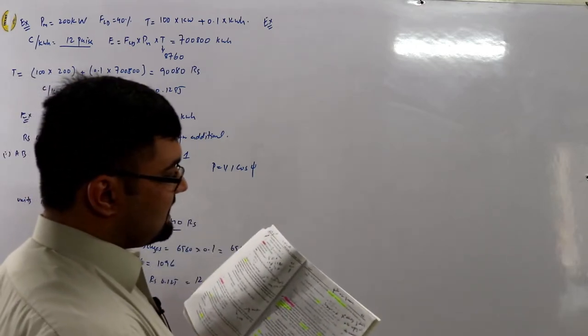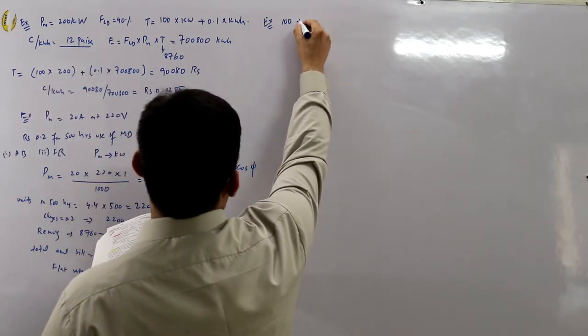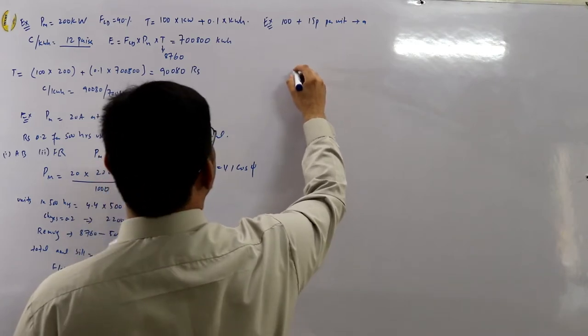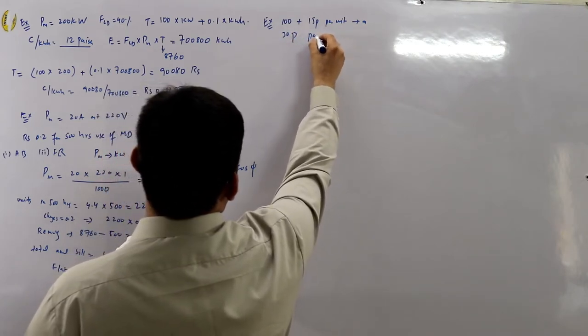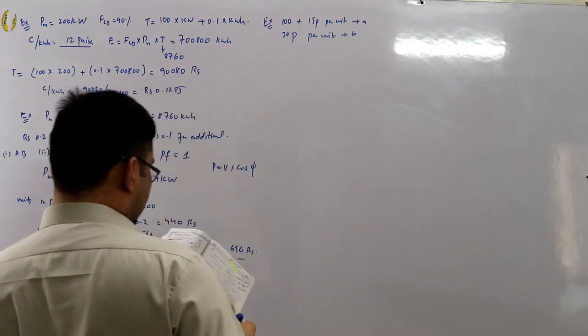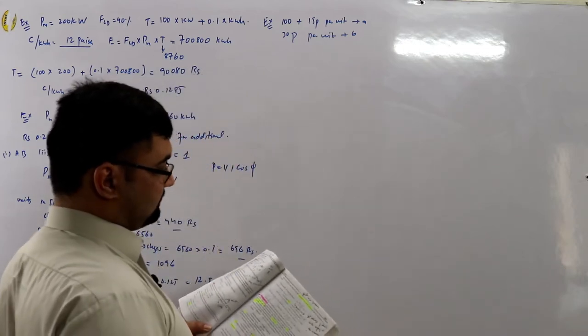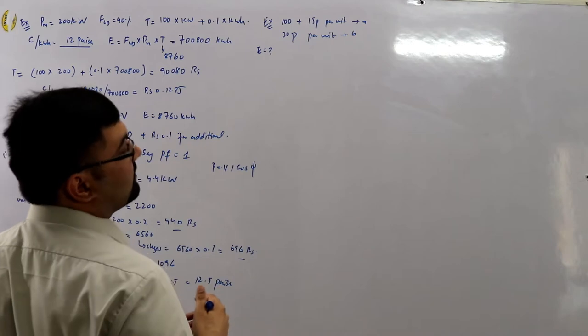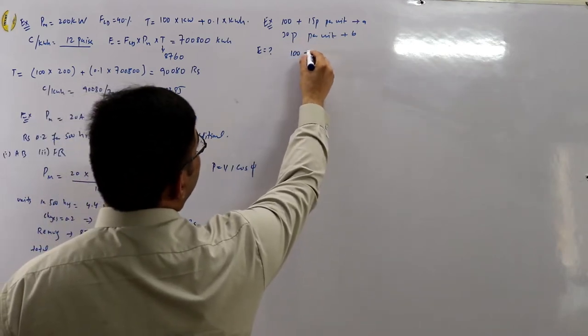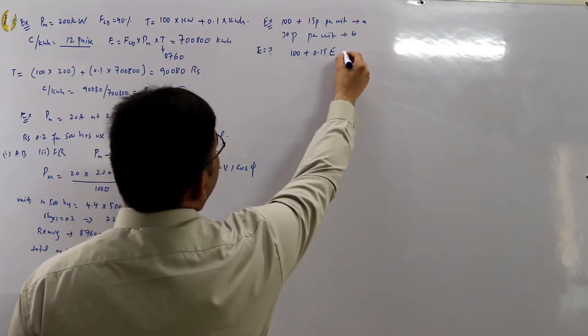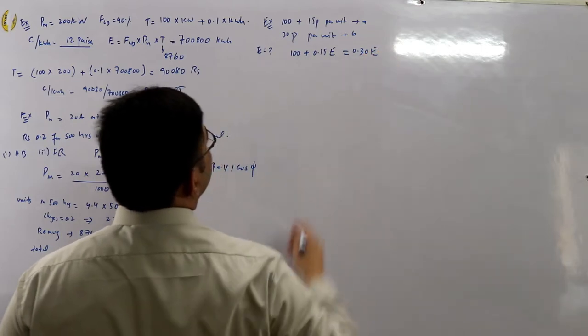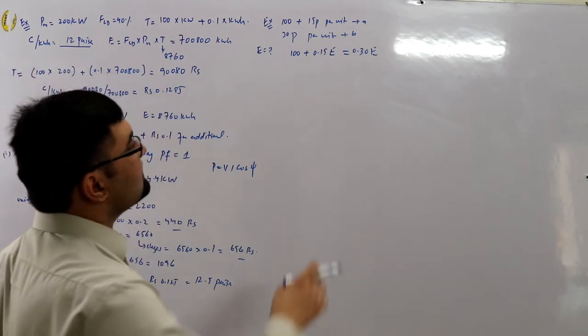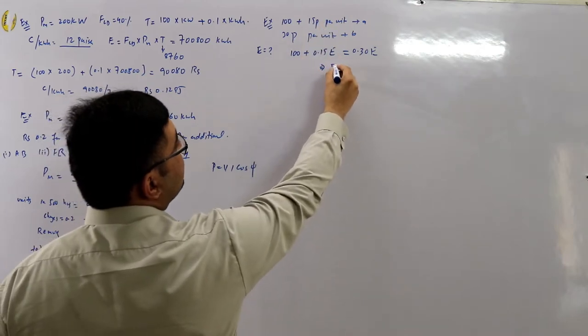Example 5.3: Two tariffs are offered — Tariff A: rupees 100 plus 15 paisa per unit; Tariff B: a flat rate of 30 paisa per unit. At what consumption is the first rate economical? Set up the equation: 100 + 0.15e = 0.30e.